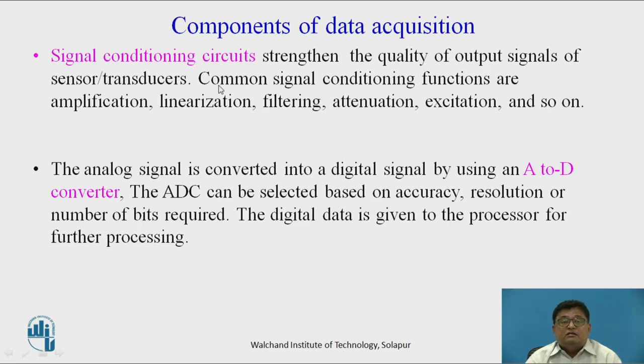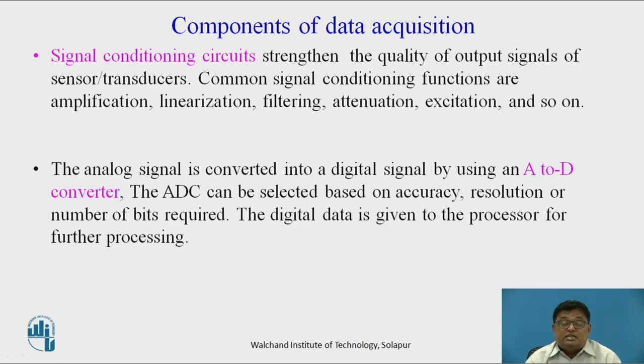The signal conditioning circuit is used to increase the strength and quality of the output signals from the sensor or transducer. For example, the output of some sensors may be in millivolts, so it needs to be amplified for further processing. Or the output may be a change in resistance, which needs to be converted into voltage. Signal conditioning circuit functions include amplification, linearization, filtering, attenuation, and excitation.